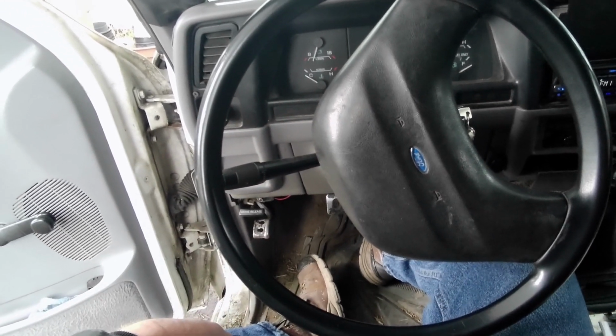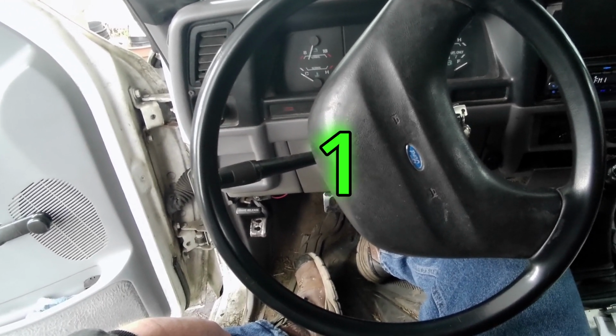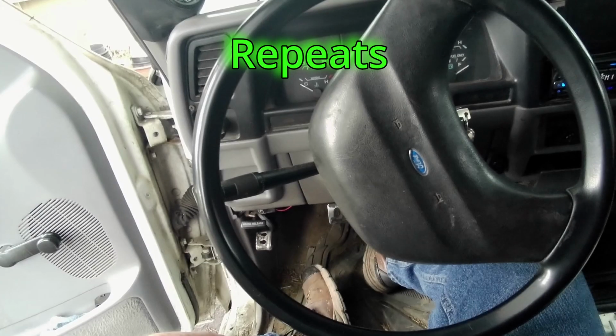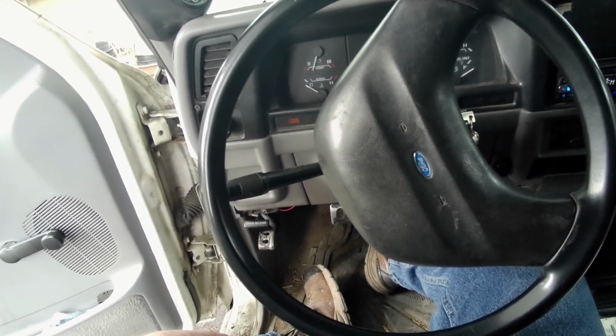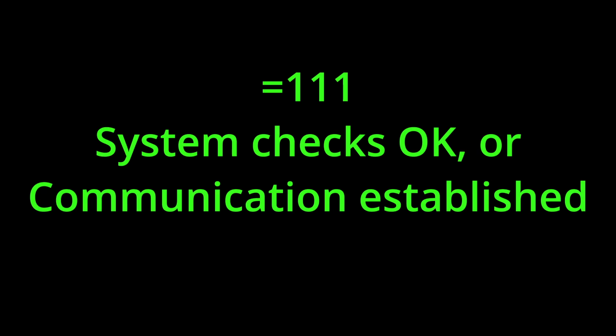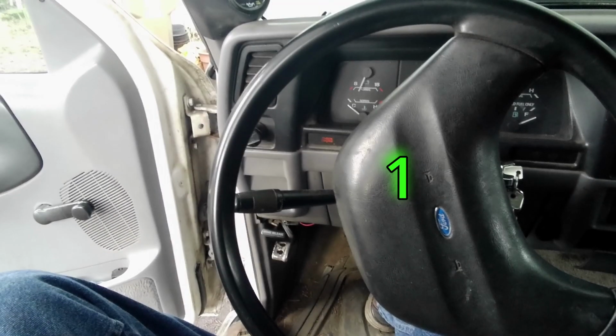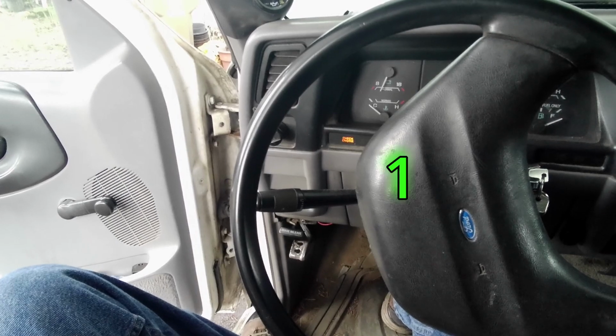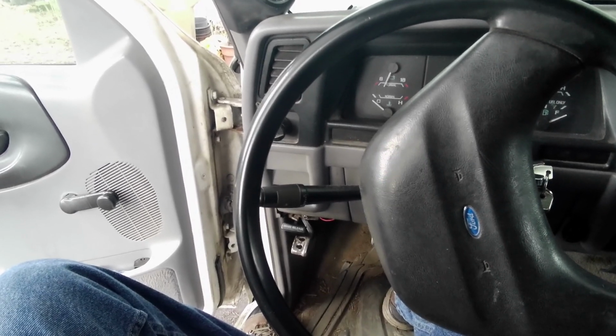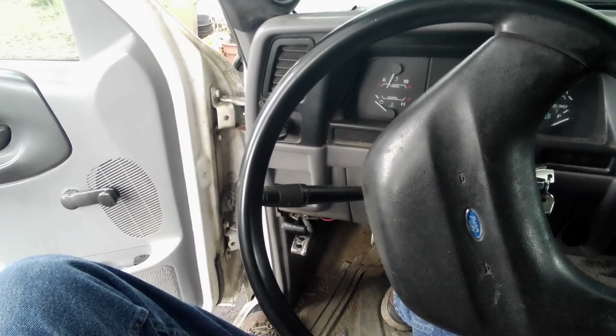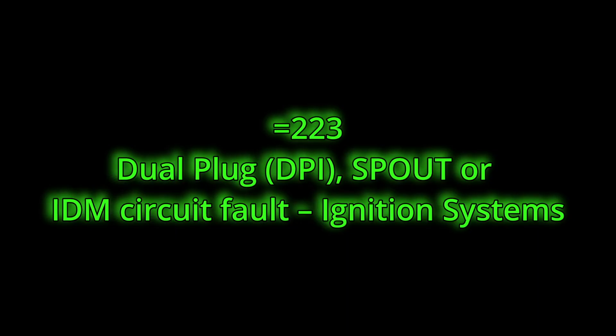1, 1, 1 equals 111, and then it repeats. 111 indicates system checks OK. Communication is established. Next code: 2 flashes, 2 flashes, 3 flashes. This equals a 223, a dual plug DPI spout or IDM circuit fault.